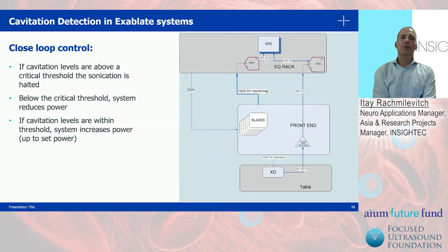Here we start to talk about the closed loop control, which plays a very important role in our treatments. Basically, we would like to control the cavitation. In the beginning, we had only a stop sonication mode, which meant that once there was a cavitation that was reaching a threshold of safety, we have several thresholds of safety that we have basically found by the pre-clinical experiments that we have done prior to the first submissions that led to the treatments. So if the cavitation level would go to these levels, the sonication would stop. And in that case, many treatments would stop.